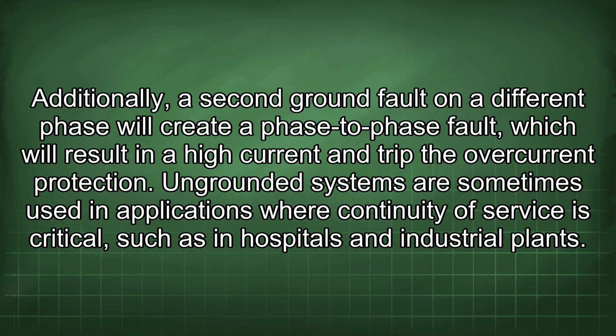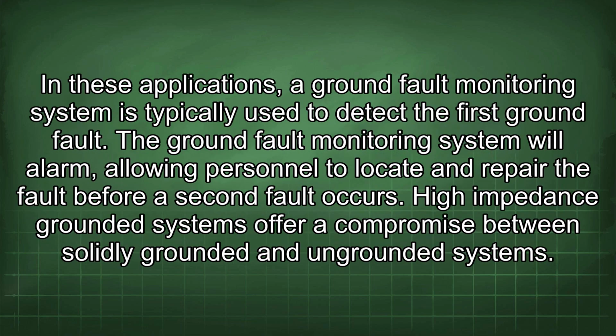Ungrounded systems are sometimes used in applications where continuity of service is critical, such as in hospitals and industrial plants. In these applications, a ground fault monitoring system is typically used to detect the first ground fault. A ground fault monitoring system will alarm, allowing personnel to locate and repair the fault before a second fault occurs.